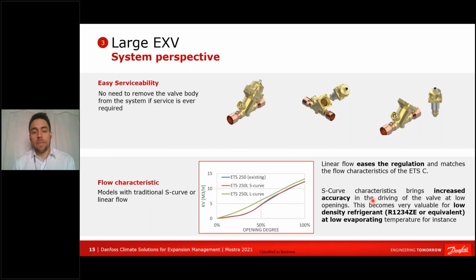Keeping talking about the ETS Large - the first picture shows why I said this has easy serviceability. You see that with the ETS Large, if you want to do maintenance on it, which you should do every year, you don't have to remove the whole valve. You just unscrew the coil, check that everything is okay, and screw it back onto the valve. This really improves maintenance, eases the job for maintenance people, and reduces the cost of maintaining your application.